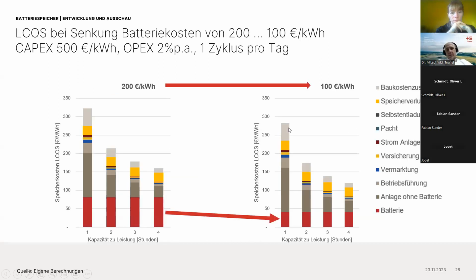Finally, I want to show you the effect when battery cost is reduced by a factor of two. Batteries used to cost about 200 euros per kilowatt hour; let's assume this goes to 100. I want to show that, as I mentioned, if these overhead costs don't scale down, you only come from 32 cents per kilowatt hour to 28—not big. But if you come from 15 cents down to 12 cents per kilowatt hour, that's interesting.